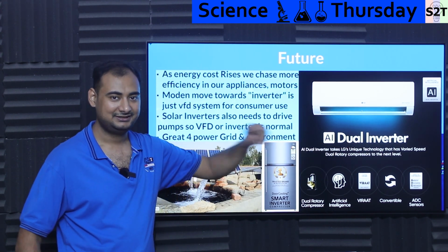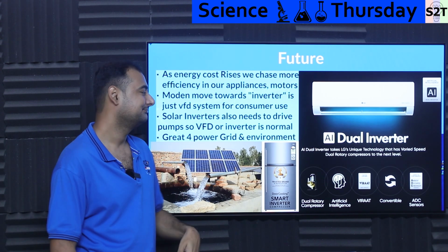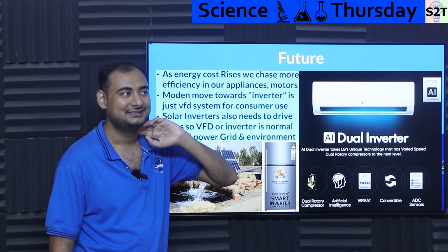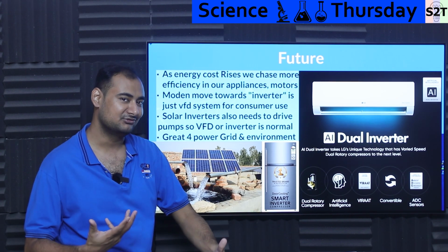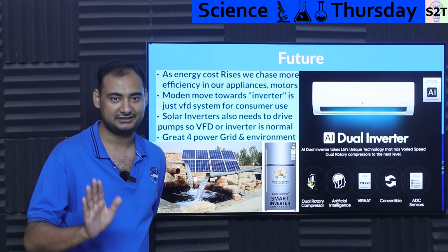What is an inverter? DC to AC. What is a VFD? AC to DC, DC to AC. That's why we call it an inverter. Do not ask me why we do not call it VFD technology, but apparently somebody in marketing thought that VFD is a complex, engineering word, so let's call it a simple word like inverter. It's just marketing. Let that be very clear.